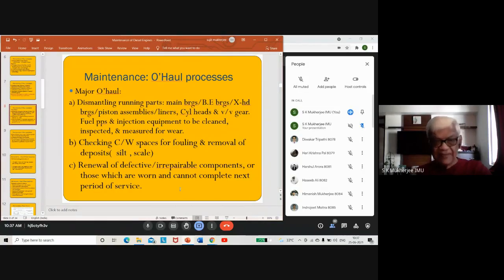So why is this damaging? Why is this little bit of silt damaging? And which part is most damaging? This silt, it can cause damage to the circulating pumps. See, the pumps, when they're working, they have what are called shaft seals. The shaft seals are very precision equipment. That means the sealing of the surface is on a very smooth surface. It consists of a carbon ring and a stainless steel ring. Both are pressed against each other to provide an absolutely smooth surface.